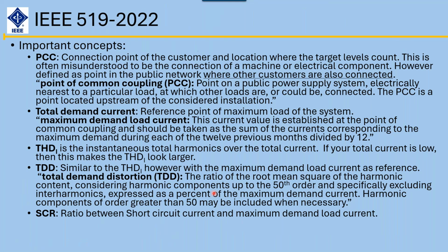So here are some definitions we need to talk about, and I'll talk more about these in further slides. The first is what we call the point of common coupling. IEEE 519 does everything based on the point of common coupling. That's the point where you meet your neighbor. At that point, they want to make sure your voltage isn't low enough to cause the customer next to you to have issues, because if the voltage goes down, the current goes up. So you're not going to create current issues for the customer. This is the PCC, and I'll show more on that.